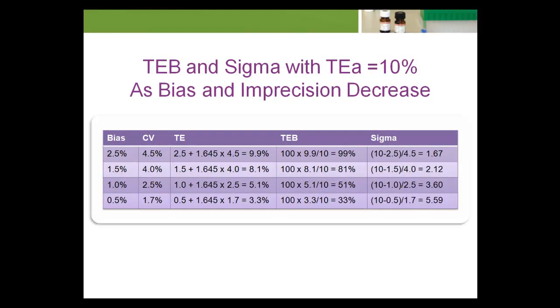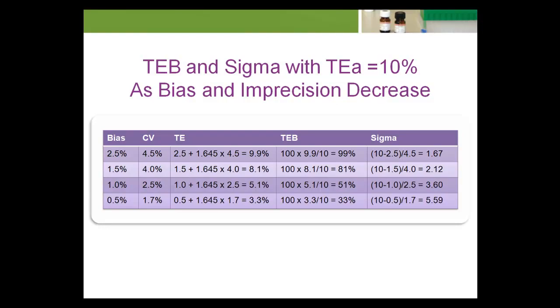We have already shown that sigma values can be used as a guide to the amount of QC effort required to assure that the lab's quality requirements are met. The TEB is a quantity that relates process capability to quality requirements. This table computes both TEB and sigma values, assuming TEA equals 10 percent, for different amounts of test system bias and imprecision. In the first row, the bias is 2.5 percent and the CV is 4.5 percent. In this case, TE is 9.9 percent using the 95 percent limit definition, TEB is 99 percent, and the sigma value is 1.67. Thus, a process where nearly 100 percent of the TEA is consumed by the test system's bias and imprecision is associated with a very poor sigma value.